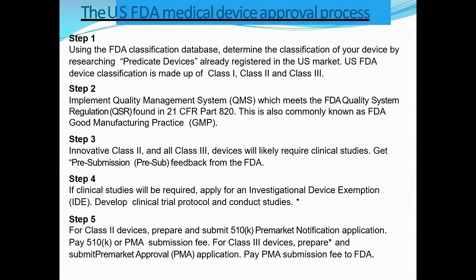So I will look into an IR thermometer, and I will select from the big brands and see how they must have taken the approval and under which category they must have categorized. So under US FDA, you will get the full list of medical devices which have already been marketed in the US. So the first step is very important: you have to classify based on the predicate devices.